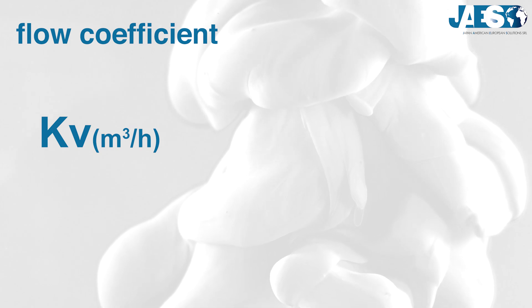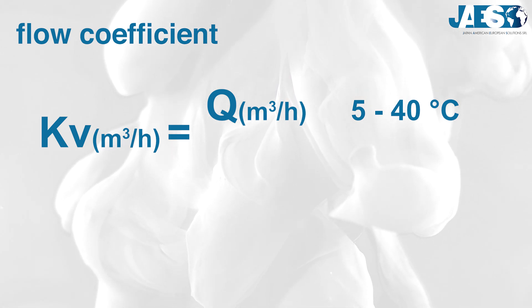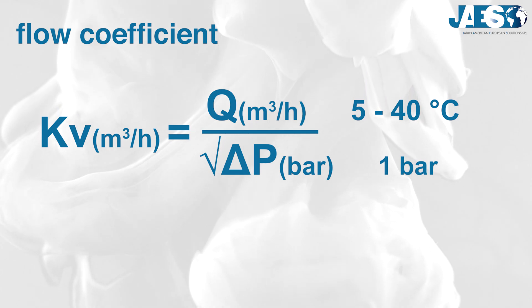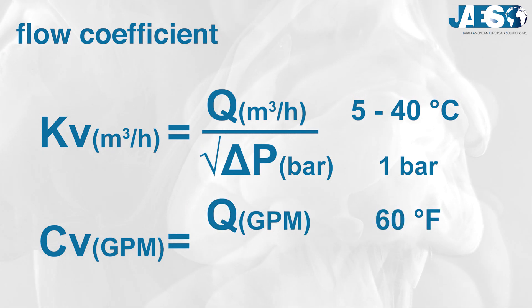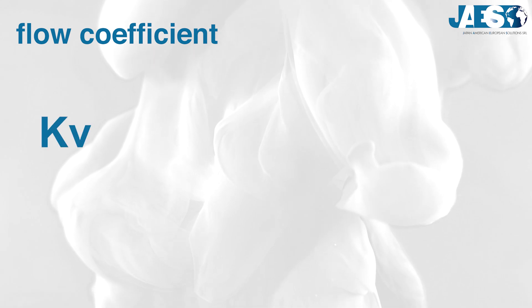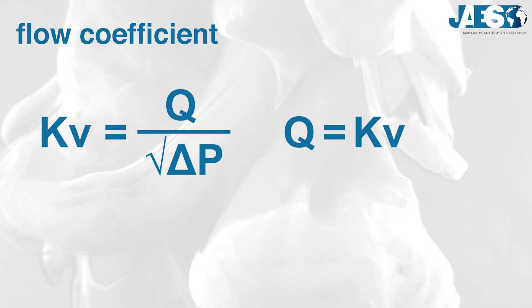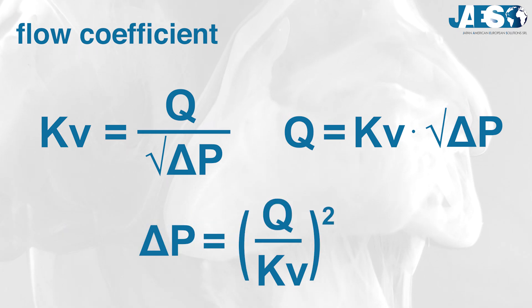One of the most important data to identify a valve is its flow coefficient. The flow coefficient, with symbol KV, describes the water flow between 5°C and 40°C, expressed in cubic meters per hour, measuring the volume passing through the valve with a differential pressure of one bar. The American system uses the coefficient CV, described as the water flow at 60°F in US gallons per minute with a differential pressure of 1 psi. 1 KV is equal to 1.156 CV. Using this coefficient, you can size the valve from flow rate and pressure drop, calculate the flow rate from the pressure difference, or calculate the pressure drop from the flow rate and the KV coefficient.